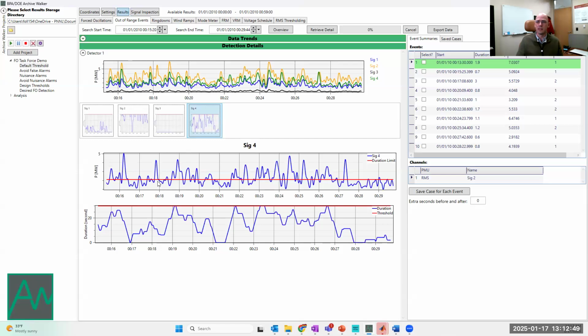And signal 4 is sort of in the middle, where we get these 4 false alarms over the course of 15 minutes. So my point here is really just that with default thresholds, you can run into this, where there's maybe more diversity in these signals than you might expect. All 4 of these signals are coming from the same reliability coordinator, but based on where they're at, they look quite a bit different.